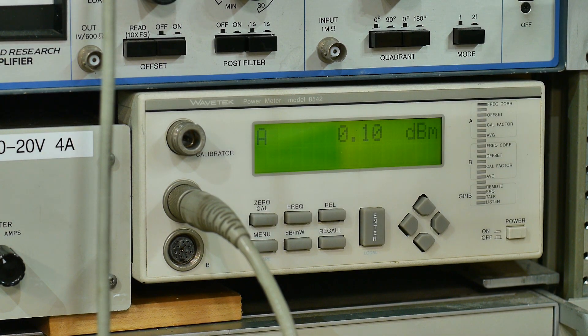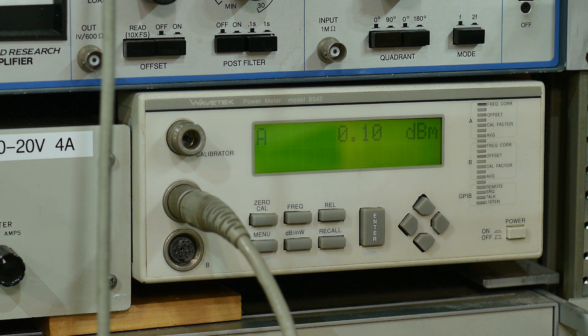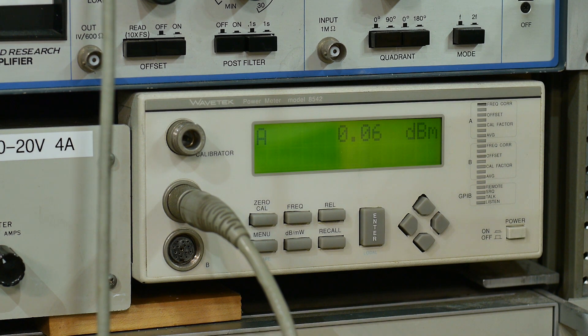So yes, indeed. Yesterday when I adjusted this thing, the insertion loss tricked me into setting the power level too high. So I'm going to readjust the calibrator down. I can't see this across the room there. There we go. Going the wrong way. All right, there we go. Now I have a 0.1 insertion loss in there, so I'm going to set it 0.01 low.